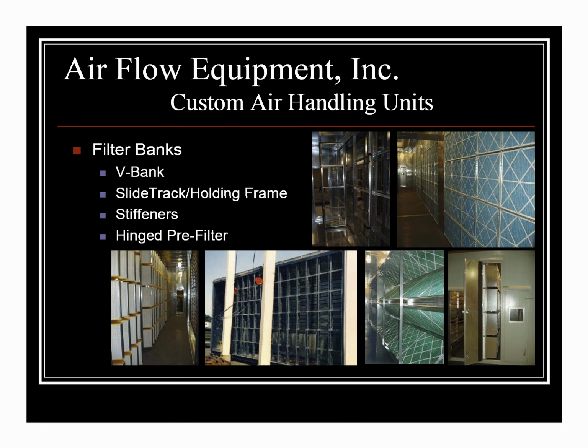We scratched our heads for a while on that one and ultimately came up with this hinged filter rack. Basically you've got a row of filters mounted on a hinge, almost like a door. You turn a latch, loosen the filter door, open it up, step through, and change your final filter without changing your pre-filter.